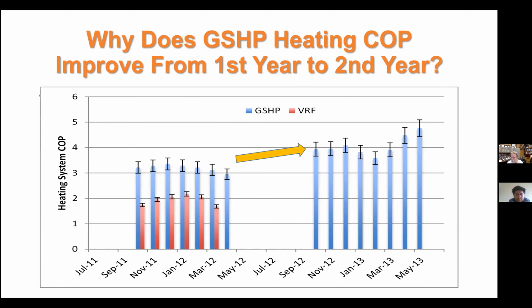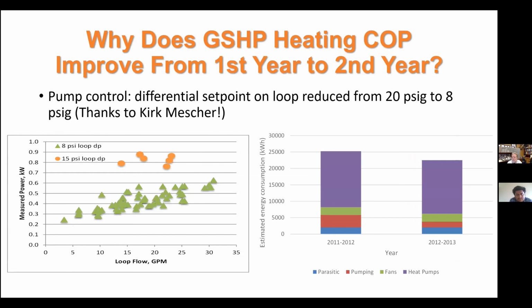So the ground source heat pump system, this increase from the first year to the second year is related to the pump control. This is a central pumping system with a control by differential set point on the loop. And up until partway through, between the two winters, the set point was set to 20 PSI difference. An engineer who's since passed away, Kirk Mesher, was an expert on ground source heat pump system design. He was at ASHRAE headquarters and looked at the gauge in that mechanical closet and said, oh, this setting's way too high. So they changed it down from a 20 to 8.